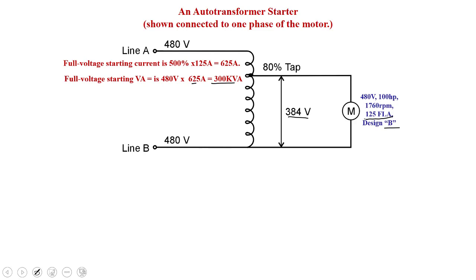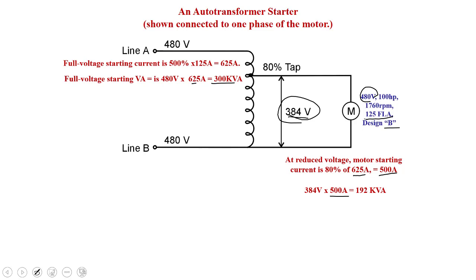This is where the reduced voltage starters come in. We're going to try to drop that kVA down using an auto transformer. If we reduce the voltage to the motor, we reduce the current, and we can get the VA of the motor down during startup. At a reduced voltage, if I only supply this motor with 80% of its 480 volts line voltage, we reduce the current to the motor to 500 amps. So 80% of our inrush of 625 gives 500 amps. The VA used by the motor is our voltage of 384 volts times 500 amps, so now we're only using 192 kVA at the motor.